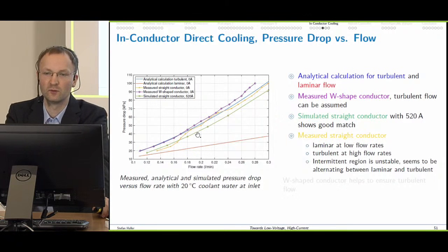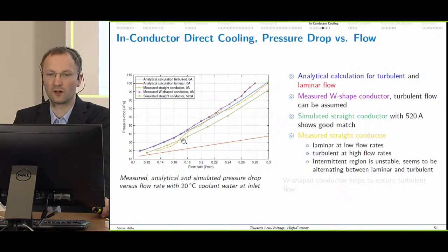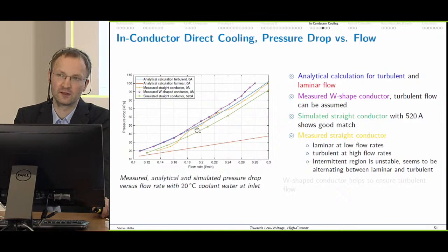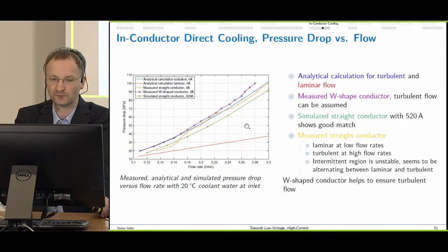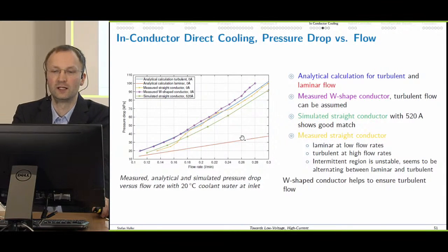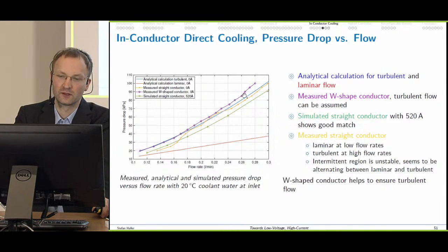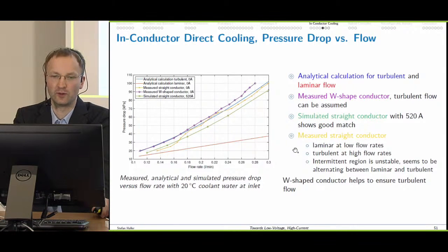So usually we would assume a temperature gradient from the coolest to the hottest place. But sometimes we get a sudden change there, which is in the first 25 to 40–50% of the conductor. So we assume it's due to the design of the coolant inlet there. So this is something for future work to investigate. The takeaway message here is that the W shape of the conductor helps us to ensure turbulent flow and thus to increase the heat transfer into the coolant.